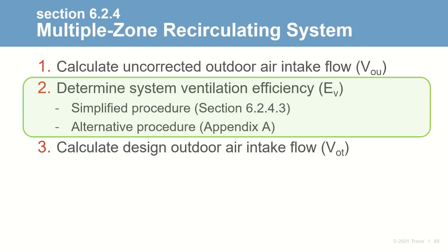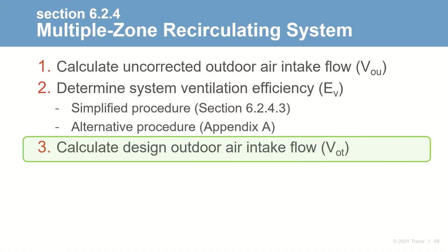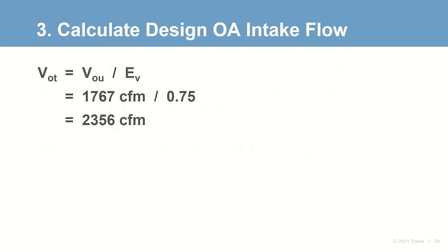The standard also includes an alternative procedure for calculating System Ventilation Efficiency in Appendix A, which we won't walk through today. The final step for a multiple zone recirculating system is to calculate the Design Outdoor Air Intake Flow V-sub-OT: the uncorrected outdoor air intake flow of 1,767 CFM divided by the System Ventilation Efficiency of 0.75, giving a Design Outdoor Air Intake Flow of 2,356 CFM.